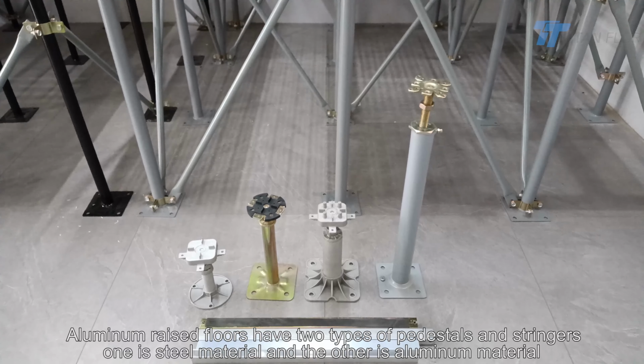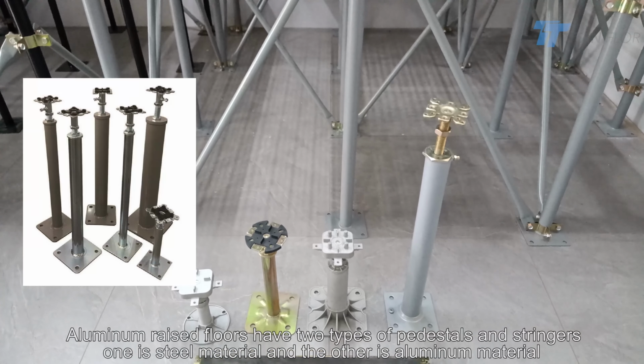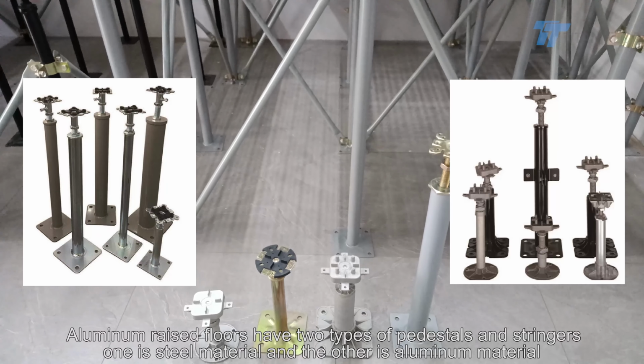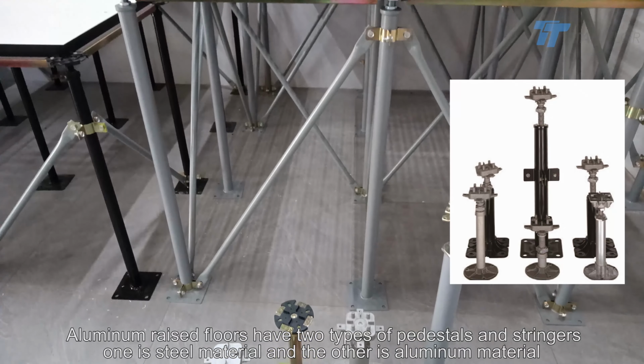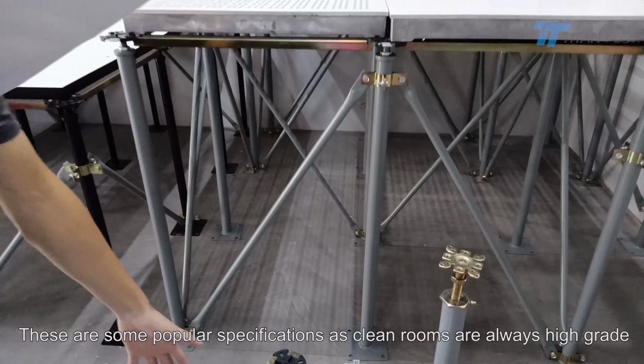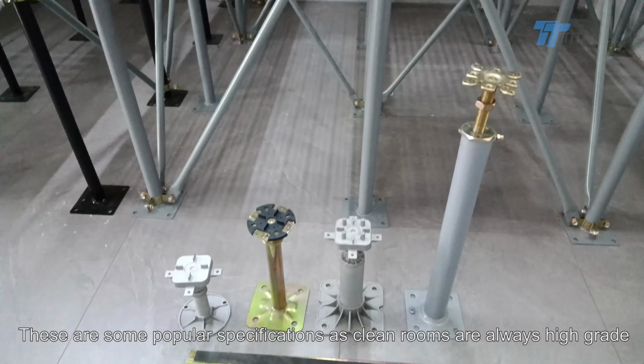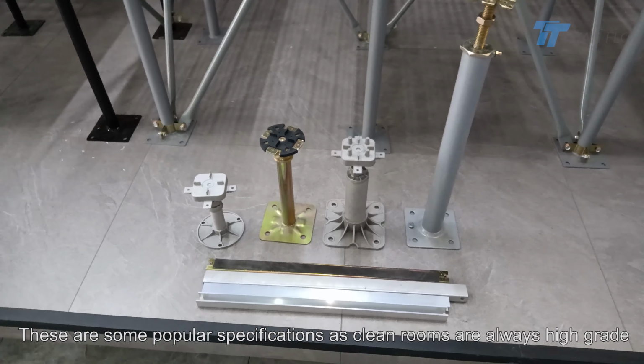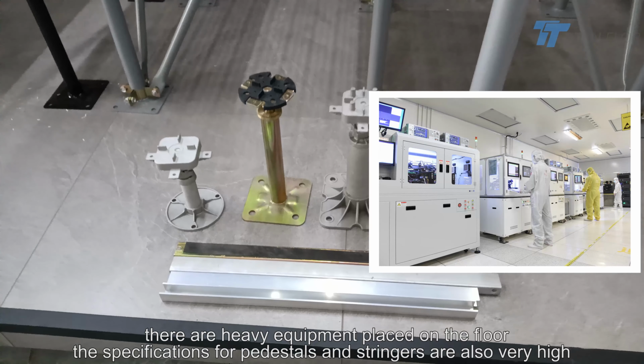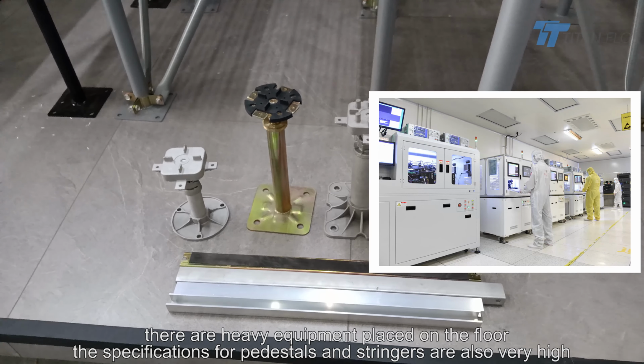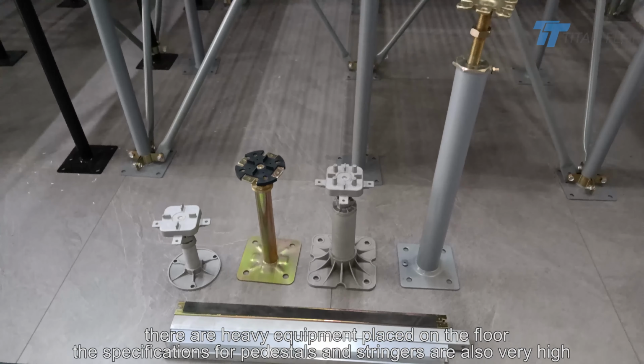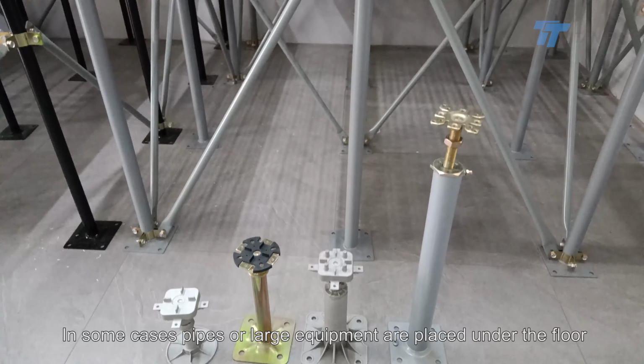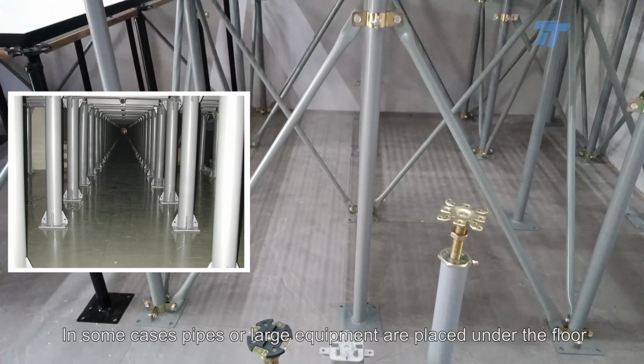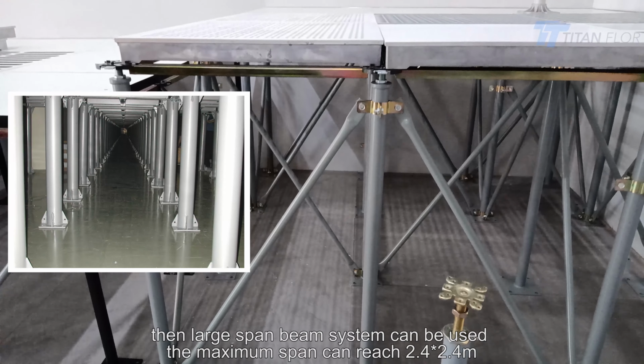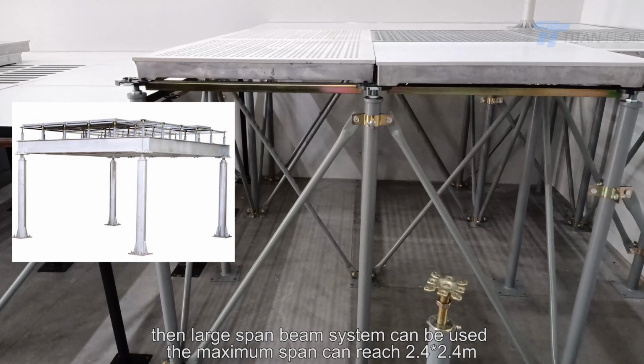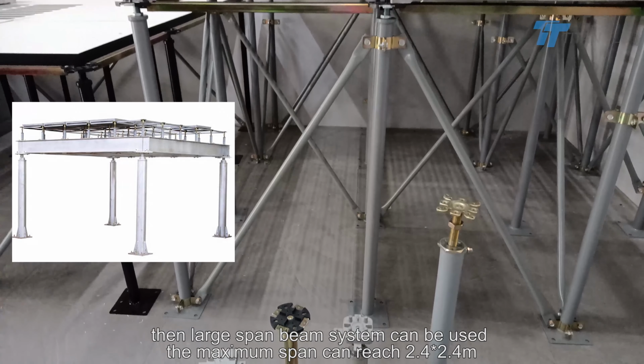Aluminum raised floors have two types of pedestals and stringers. One is steel material, and the other is aluminum material. These are some popular specifications. As cleanrooms are always high grade, there are heavy equipment placed on the floor. The specifications for pedestals and stringers are also very high. In some cases, pipes or large equipment are placed under the floor. Then, large span beam system can be used. The maximum span can reach 2.4 meters.